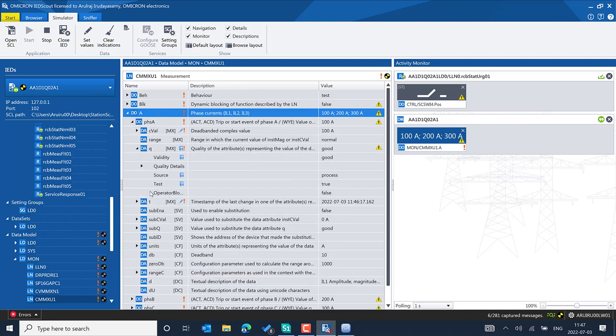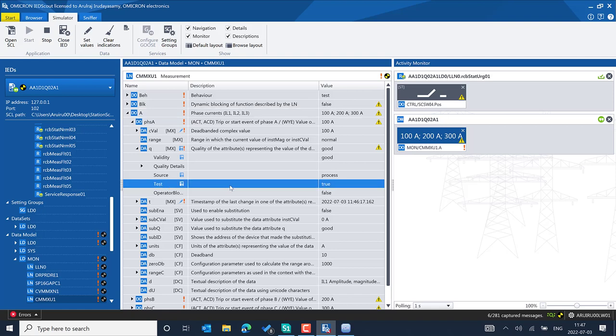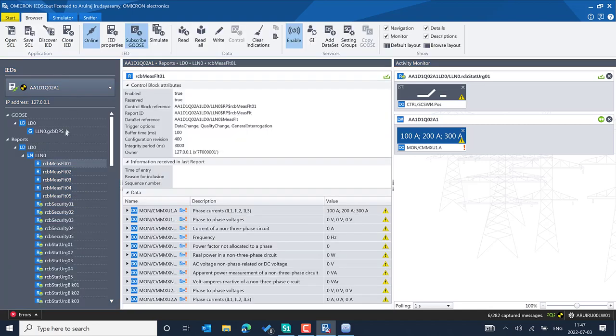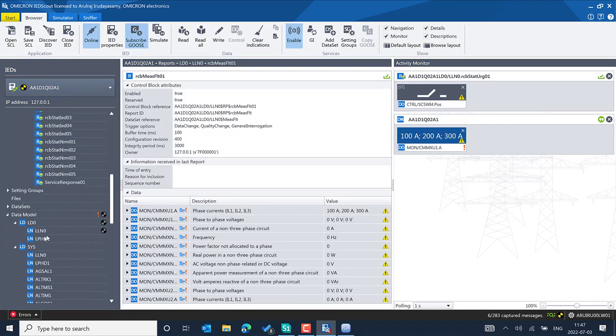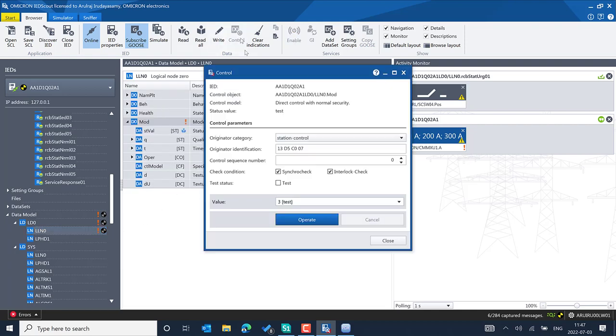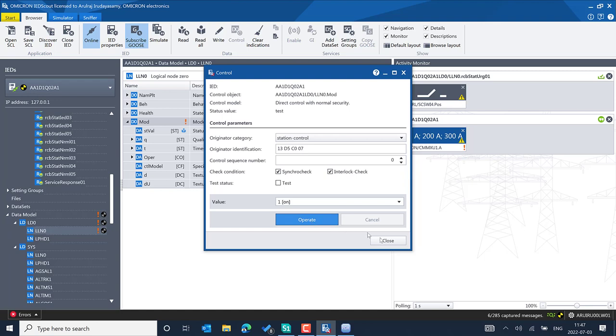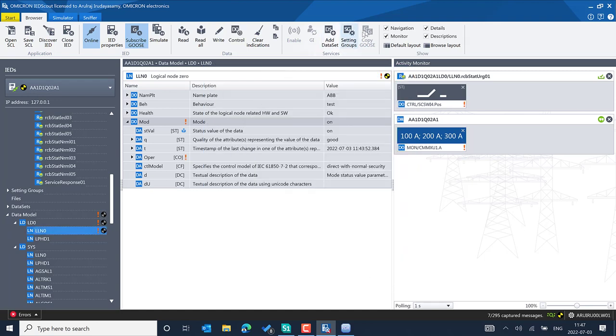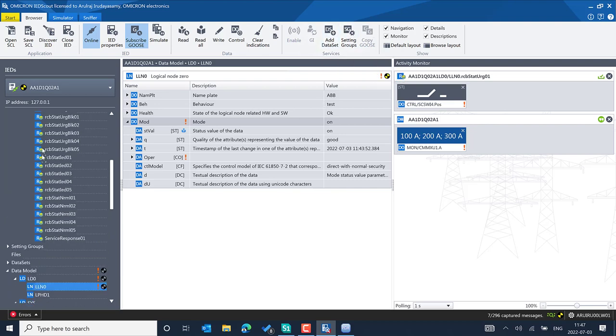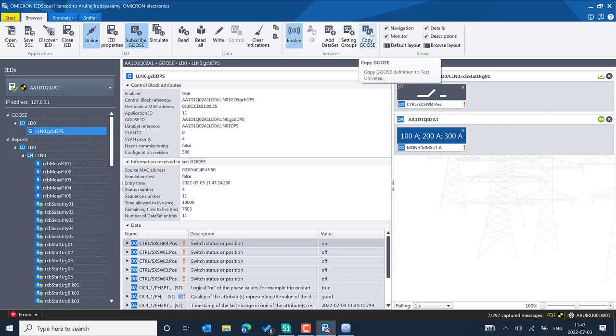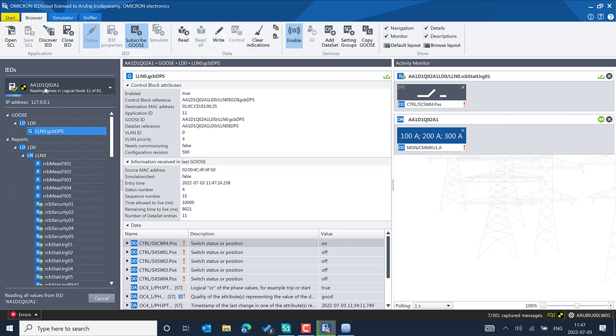When working with IED Scout, you can see values with quality in detail — for example, the quality data attribute shows 'test source: true,' because the IED was put into Test mode. You can then disable Test mode and return the IED back to Normal mode.